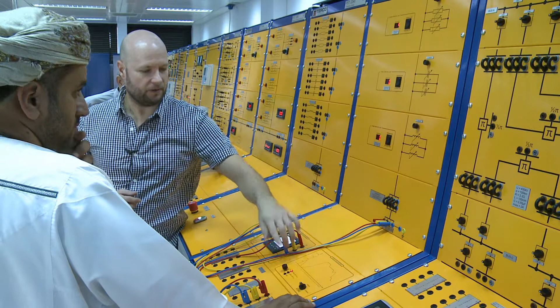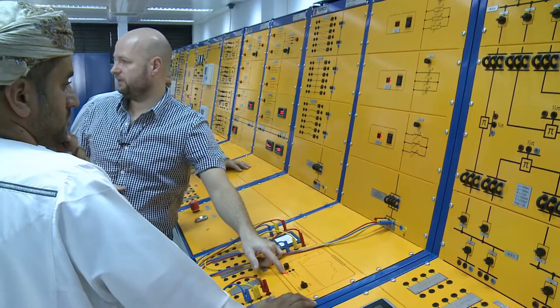So if I go back to program, we have upper limit 9, lower limit 1, and rate. Let's make that the fastest. And we go back. Is there any different rate for the load cycle? Yes. So we can change from 0 to 1 or 2 or 3, and it can go half a minute, 1 minute, 2 minutes, 4 minutes, 5 minutes between each switch. Now it's, I'm not sure, 5 seconds or something. It's very fast, and going back from upper to lower with the same rate. It's just the time between each of these time points.